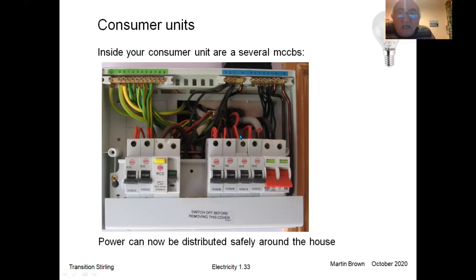16, that might be some sockets, might be downstairs sockets, upstairs sockets, something like that. Slightly thicker wire. 32 here, I think that's probably thicker wire. That might be a cooker, or it might be a shower unit or something like that. So in a consumer unit, you've got some MCCBs for the lighting, you've got some for the sockets, and you've got some for heavy circuits, like cookers and showers, and you might have one for the garage as well, so the garage can be protected, for example, as well as the main switch.